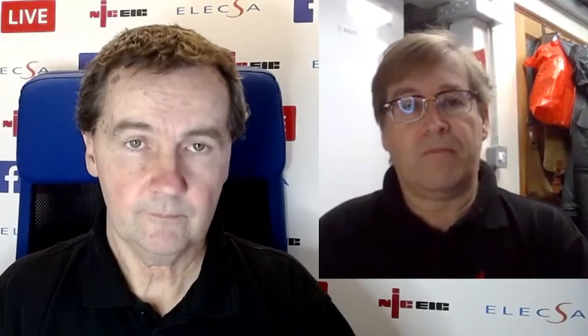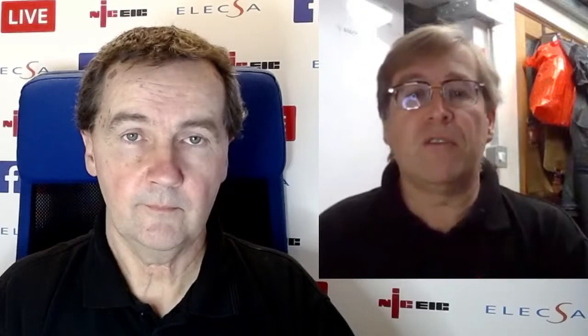Okay, so the question that we put out on social media earlier today, I think we gave people a chance to vote yes or no on it, was can I use a Type C circuit breaker in a domestic installation? So what are your initial thoughts on that, Mark? Can they use a Type C in a domestic installation? Well, certainly. There isn't anything in BS 7671 that prohibits the use of a Type C. It's just that we traditionally think of Type C devices where you've got any type of inductive load, and that can create a bit of inrush current. So Type Bs we think of for domestic use predominantly.